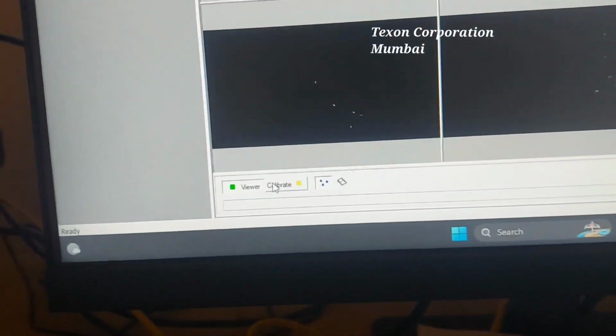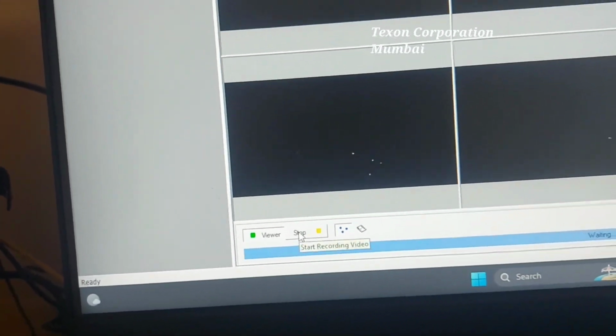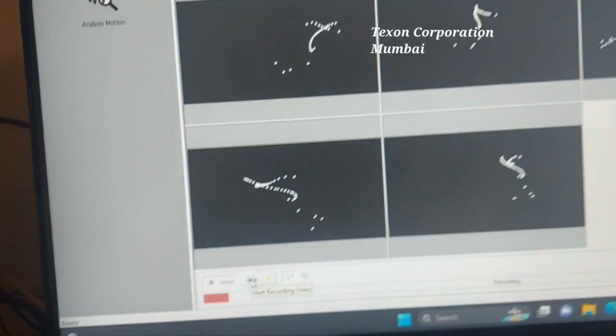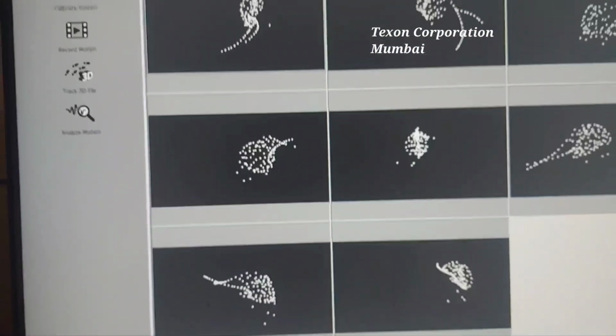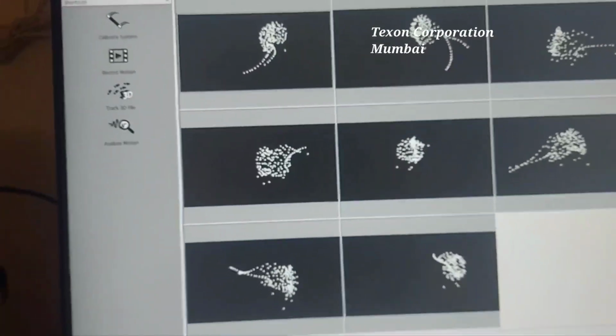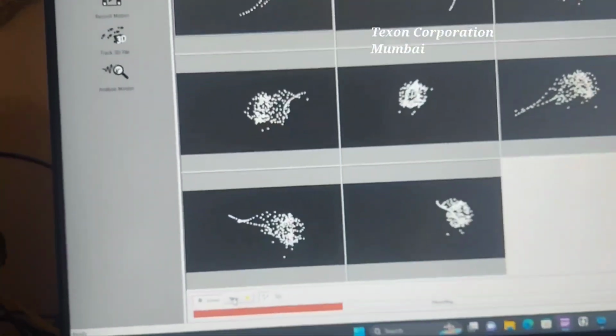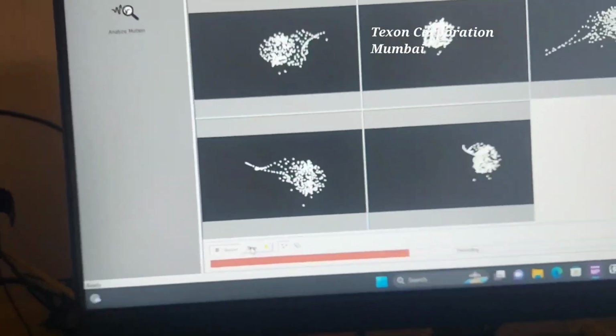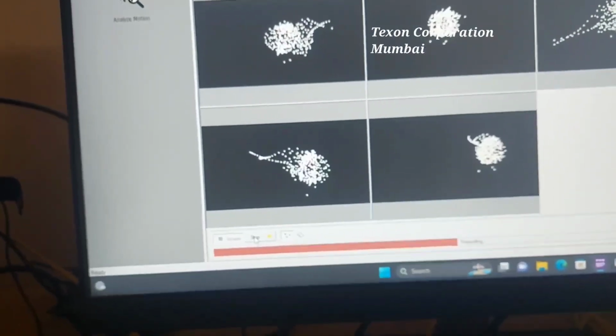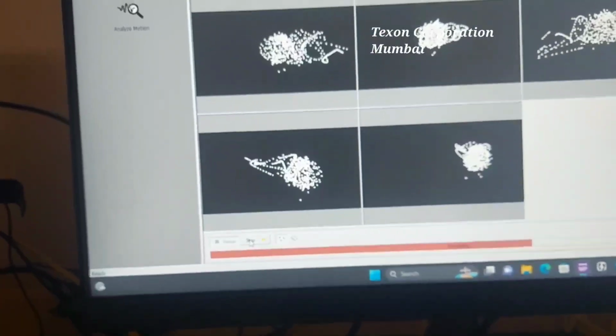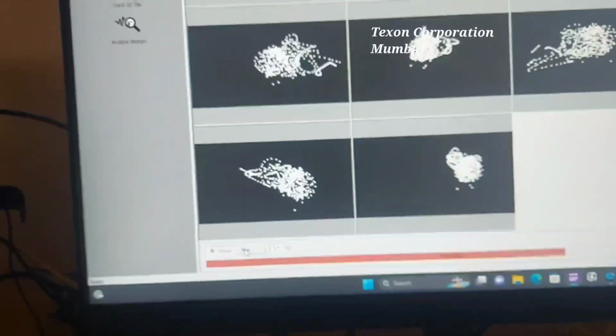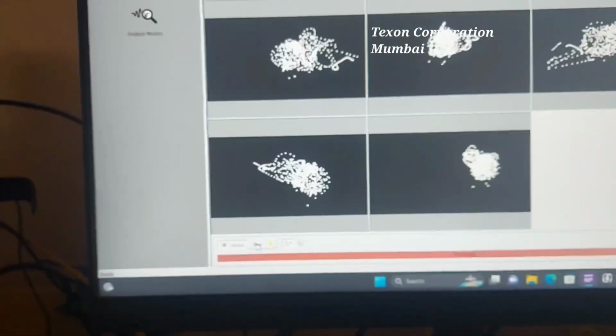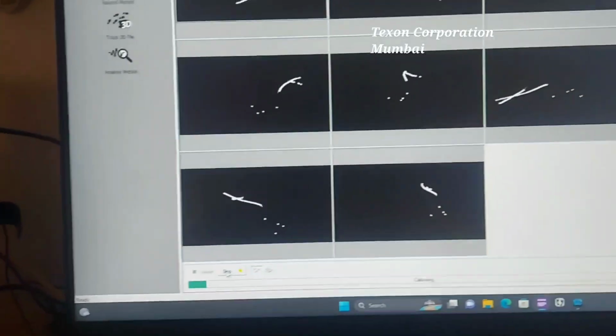Then we have to click on calibrate, and we have to inform that person to move the wand around the L frame. We have to cover the maximum area so that we can get many coordinates and segments to get a more precise result. The metric of calibration should be less than 1, or 1 is okay, but we have to try to keep it less than 1.